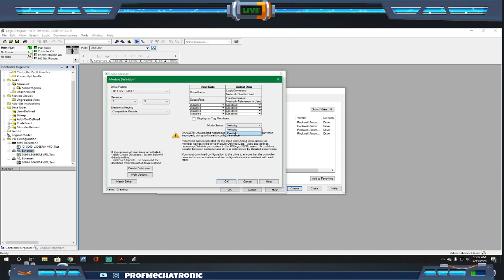We also have a mode select. Are we doing positioning? So this is more like a servo application. Are we actually using this drive to position something at specific locations, or are we using it for velocity? Now, most of the time you're going to use this as a velocity. The only time you would ever use this as a position is if you had an encoder built into it and you're looking for that encoder to provide specific feedback of where it is, if that's the absolute application of this. Now, we can still use velocity in a position-based system. We can still say, listen, move forward at 20 hertz until you hit a proxy, then slow down to 5 hertz till you hit another proxy, and then stop. In theory, that's the same as positioning, but it's not like servo positioning where we're using encoders to drive our system. So you want to make sure that your mode select matches whatever it is that you want.